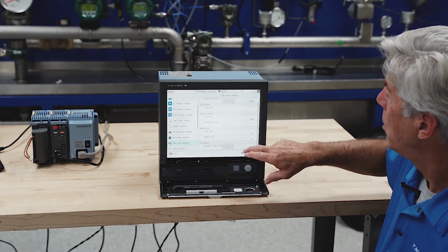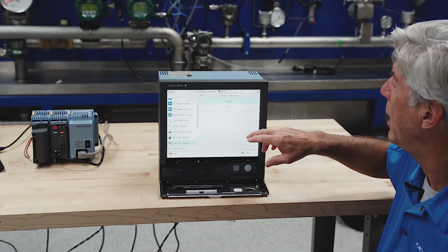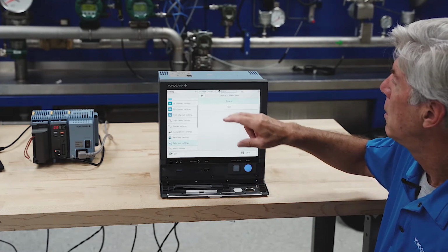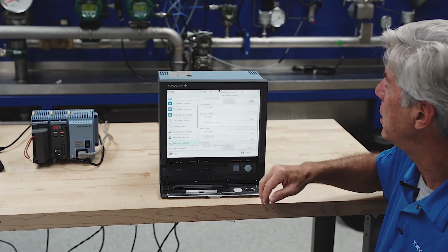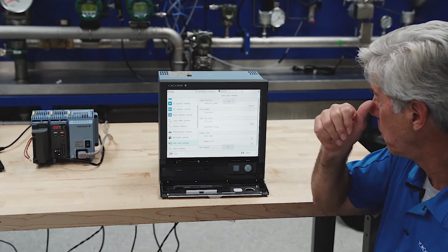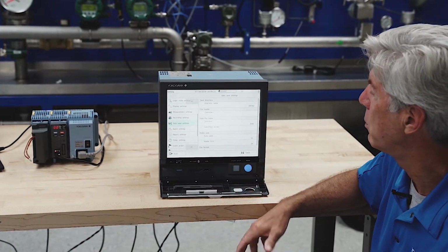Okay? On this particular recorder, you can log data in both binary and text format. Binary is a more secure format. Text format is kind of like CSV. You can open it with Notepad or an ASCII editor. But the binary format is typically what you're going to want for this particular recorder, because most of the people buy these recorders to store data, regulatory type data.